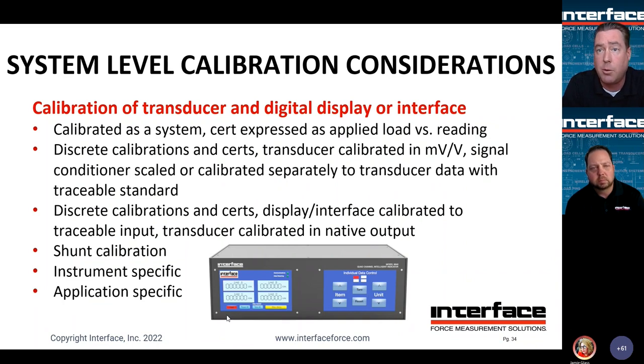This is a really nice option if you have multiple load cells with a given display, or a given display that is traveling around that you need to make sure remains traceable, or if it gets damaged, for example, in transit, you don't have to send everything back for calibration. You could simply replace a discrete item. You can also perform shunt calibration in this situation. These are very instrument specific and also application specific in terms of how these are addressed. If there's any questions on that, please contact us. Like I said, there's a lot of different options and ways to address this. Slide, please.